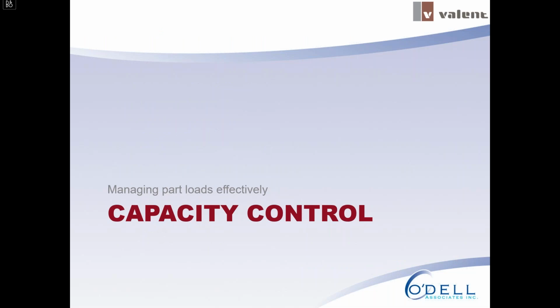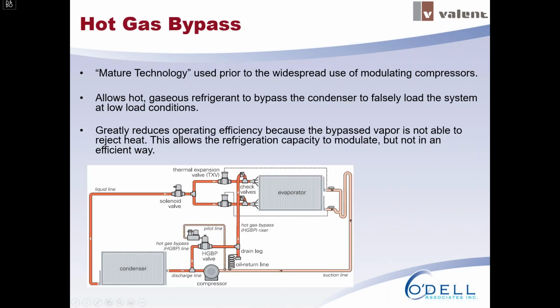So, like I said, modulating reheat is very important for controlling the leaving dry bulb temperature, but modulating the evaporator capacity is also important. And I'll talk about some methods to do that here. The first method I'll bring up is hot gas bypass, and this has been used in the past. It's an older technology, and it works to modulate the capacity of the evaporator, but it's really not an ideal solution.